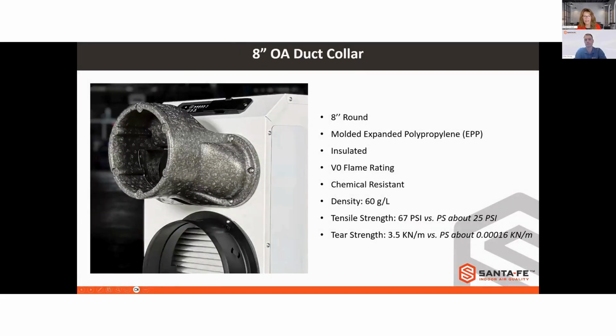So Dan, I'm going to have you tackle our new 8-inch duct on these, the 100, 125, and the 155, because I know that we've got some out in the field and there's been some questions on this new material. Yeah, sure. Thanks, Nikki. Just to dive into the ventilation duct a little bit more, it is different than our traditional polypropylene hard plastic ductwork that we've used in the past. And the reason we did that is we wanted a unique shape in order to keep the size of the unit small, but still have a round duct to attach to. That's the common practice in the industry, and we wanted to accommodate that. So we came up with this material.